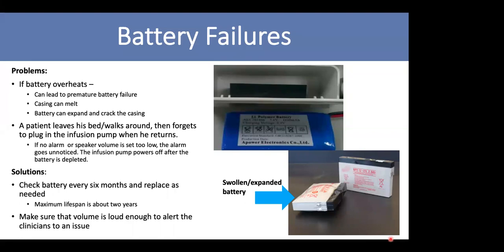You can see the expanded battery. If you don't change it and leave the old battery there, it can expand because your power supply tries to charge the battery, ends up creating heat, and the battery starts to expand. So check the battery every 6 months and replace it. The maximum lifespan of the battery is about 2 years.